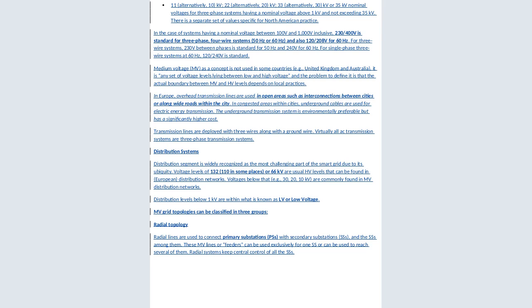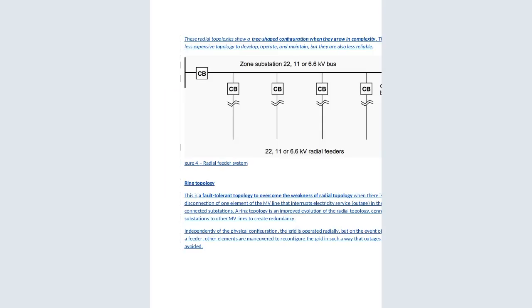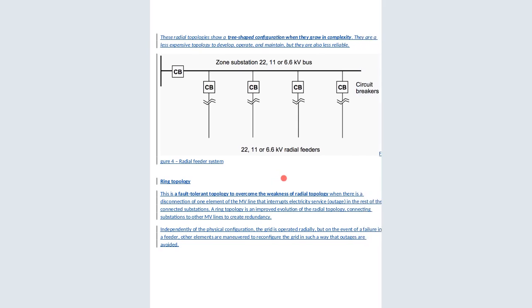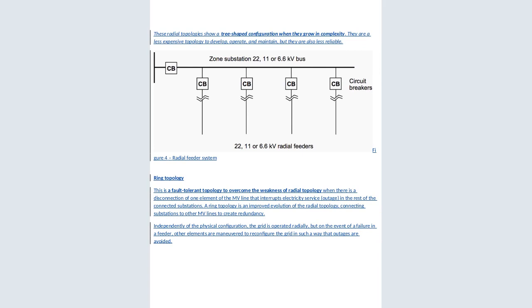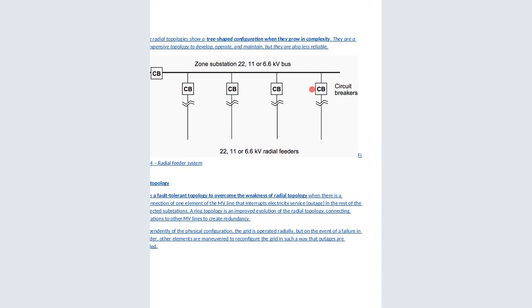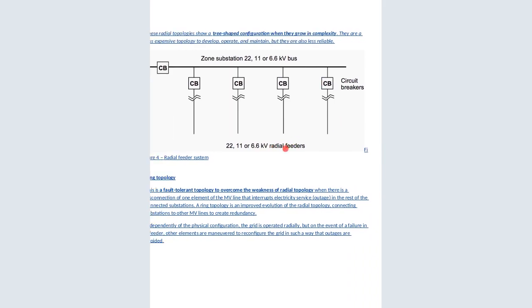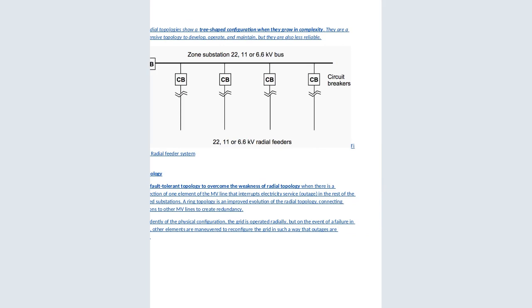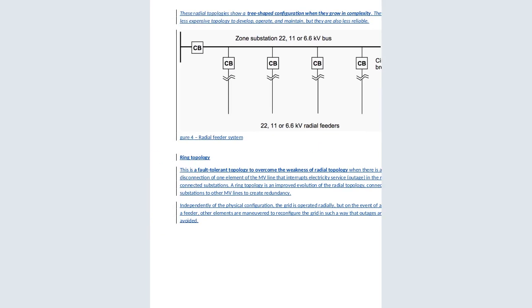Radial systems keep central control of all the substations. So we can now see the radial feeder system, the way it looks. This circuit breaker comes from the main, that is the main distribution or the transmission line, to the zone substation, that is the one for the 11 kilovolt or the 6.6 kV bus. So you can see the radial means all of them are tapping radially from the main feeder, and these circuit breakers are going to feed other substations. So the radial feeder system is there.